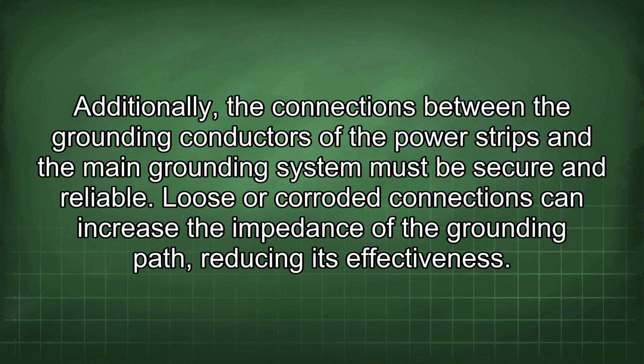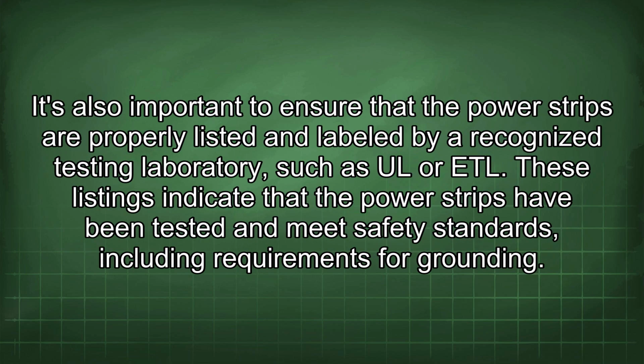Additionally, the connections between the grounding conductors of the power strips and the main grounding system must be secure and reliable. Loose or corroded connections can increase the impedance of the grounding path, reducing its effectiveness. It's also important to ensure that the power strips are properly listed and labeled by a recognized testing laboratory, such as UL or ETL.